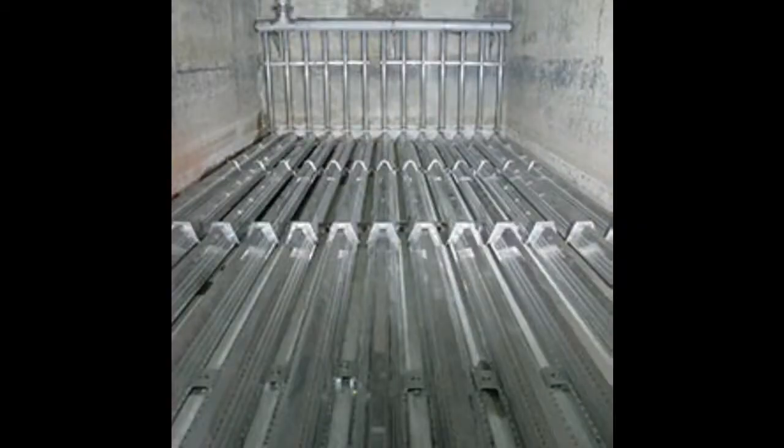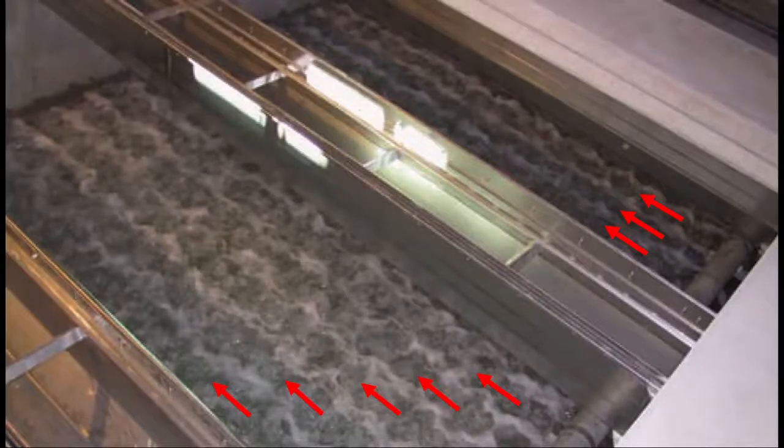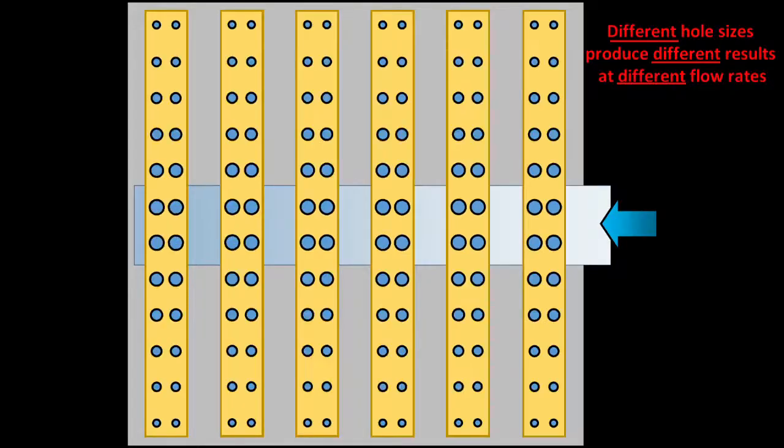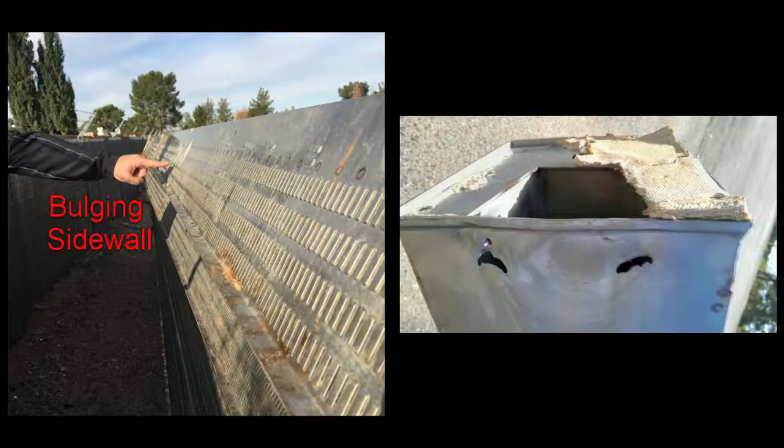Competition's triangular shaped metal underdrain laterals present three concerns. First, spacing on 12 inch centers that creates large dead zones between lateral lengths. Second, the inherent problem of maldistribution down each lateral in a header lateral configuration. And third, the questionable structural integrity of 20 gauge sheet metal.